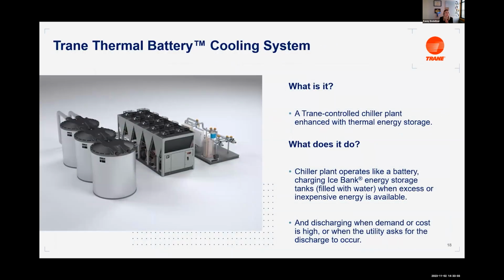Thermal energy storage utilizes what we're calling a thermal battery. Oftentimes when you think of batteries, I'm sure you're thinking of electric batteries, which are great for electric loads. But for thermal loads, what's really great is a thermal battery where you're storing that heat, in our case, by making and melting ice. And so what we're doing is helping to decouple the time dependency of your heating and your cooling. You use that ice along with air source heat pumps and chiller heaters in your building in order to heat and cool your building, and use the ice or the water in those tanks to store energy.